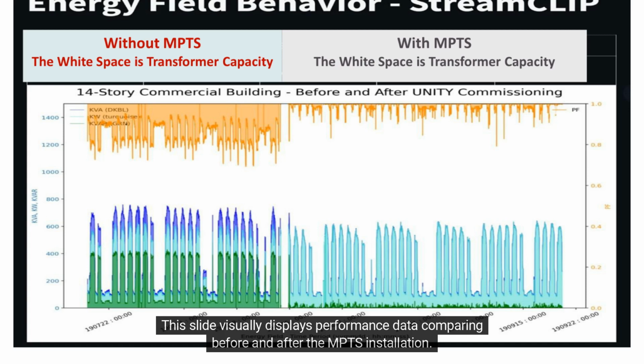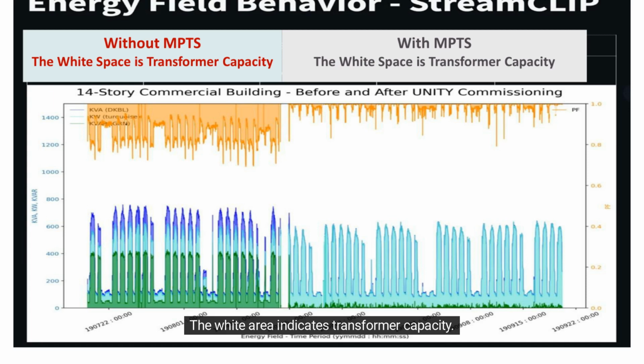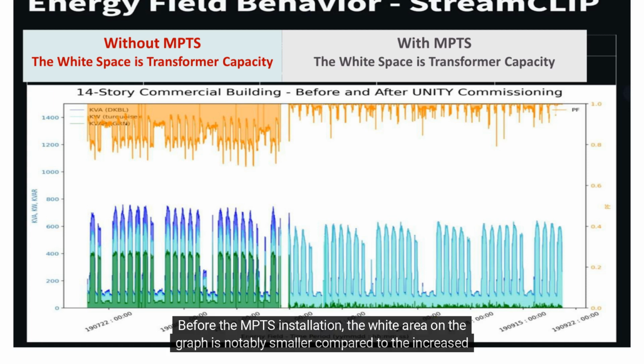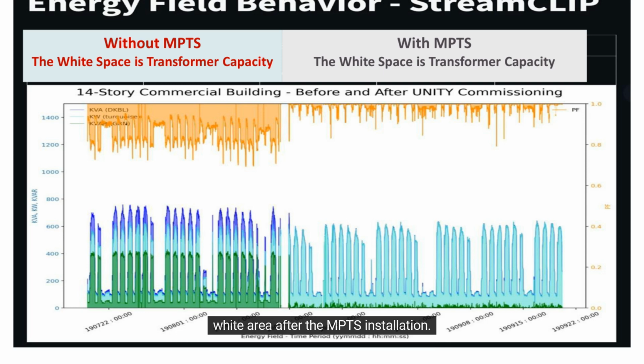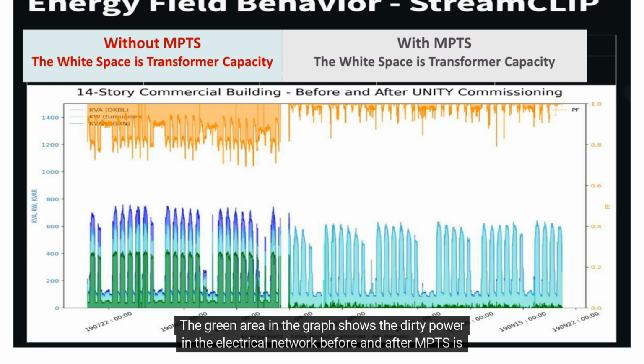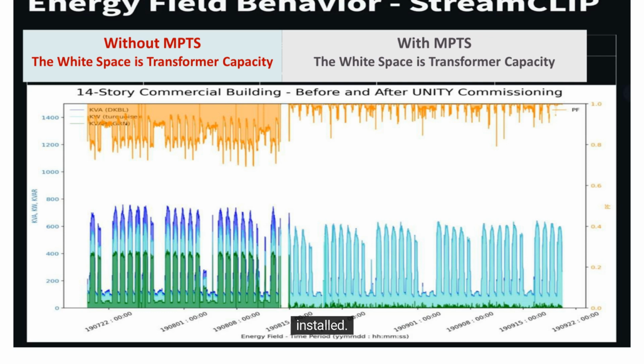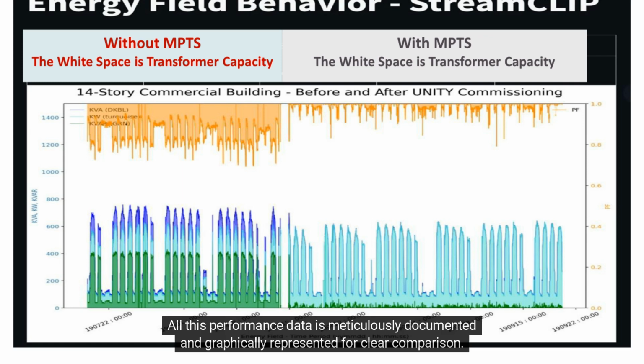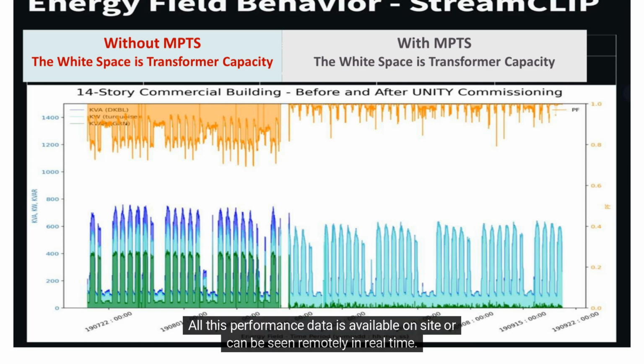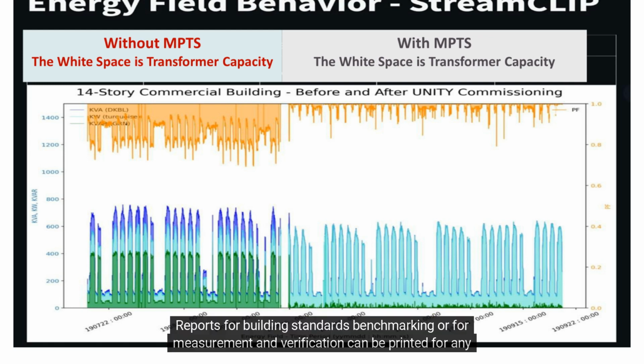This slide visually displays performance data comparing before and after the MPTS installation. The white area indicates transformer capacity. Before the MPTS installation, the white area on the graph is notably smaller compared to the increased white area after the MPTS installation. The green area in the graph shows the dirty power in the electrical network before and after MPTS is installed. All this performance data is meticulously documented and graphically represented for clear comparison. All this performance data is available on site or can be seen remotely in real time. Reports for building standards benchmarking or for measurement and verification can be printed for any period.